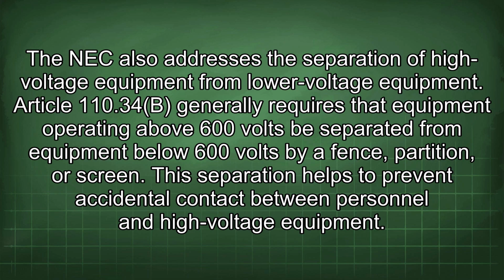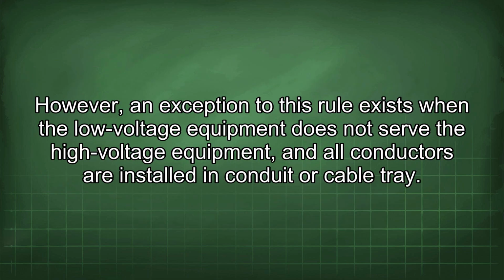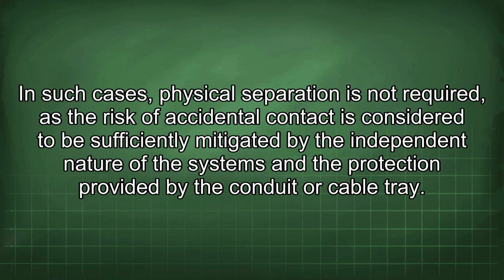Article 110.34b generally requires that equipment operating above 600 volts be separated from equipment below 600 volts by a fence, partition, or screen. This separation helps to prevent accidental contact between personnel and high-voltage equipment. However, an exception to this rule exists when the low-voltage equipment does not serve the high-voltage equipment and all conductors are installed in conduit or cable tray. In such cases, physical separation is not required, as the risk of accidental contact is considered to be sufficiently mitigated by the independent nature of the systems and the protection provided by the conduit or cable tray.